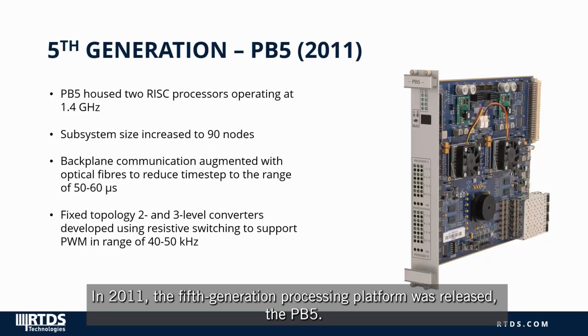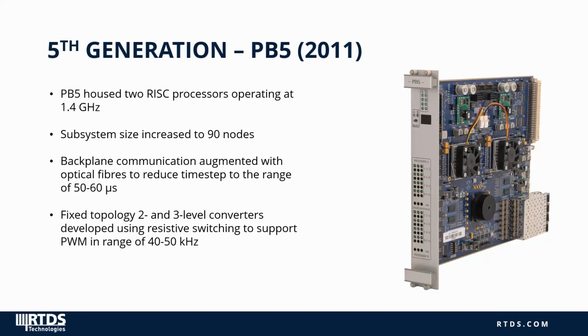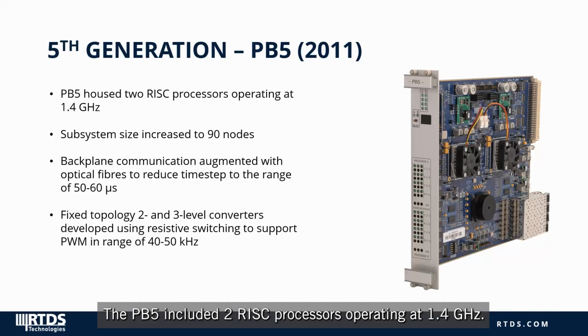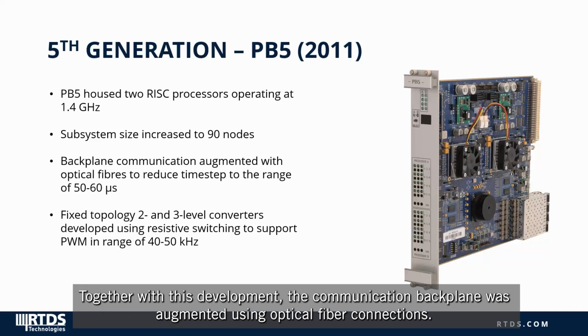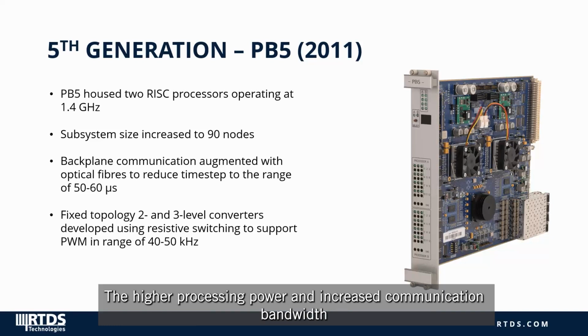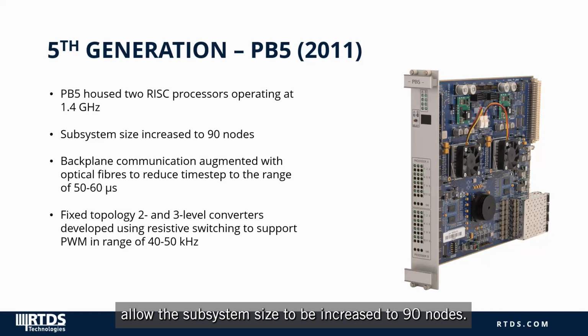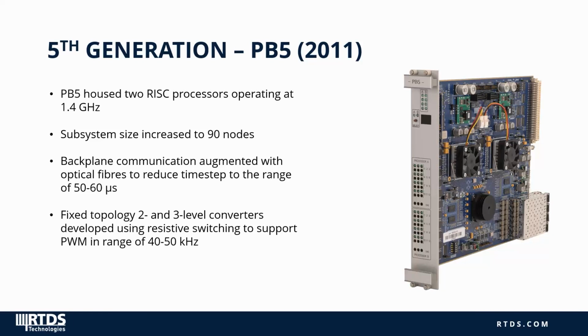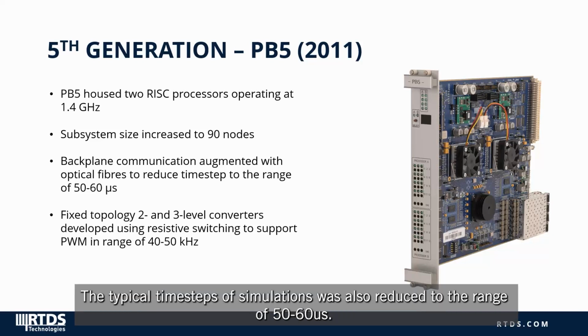In 2011, the fifth generation processing platform was released, the PB5. The PB5 included 2 RISC processors operating at 1.4 GHz. Together with this development, the communication backplane was augmented using optical fiber connections. The higher processing power and increased communication bandwidth allowed the subsystem size to be increased to 90 nodes. The typical time step of simulations was also reduced to the range of 50 to 60 microseconds.